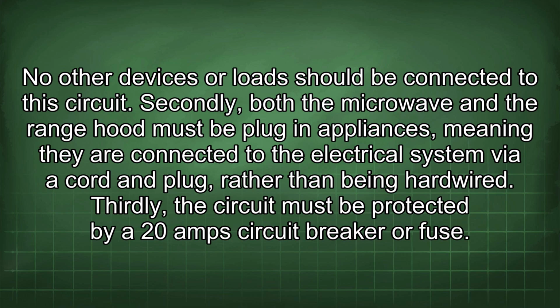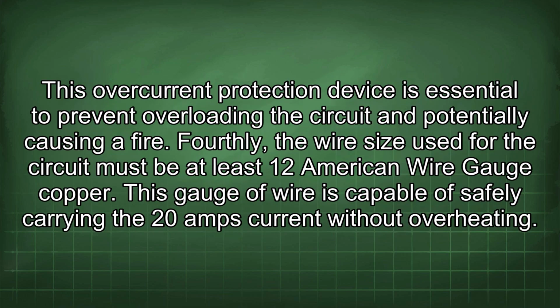Secondly, both the microwave and the range hood must be plug-in appliances, meaning they are connected to the electrical system via cord and plug, rather than being hardwired. Thirdly, the circuit must be protected by a 20-amp circuit breaker or fuse. This overcurrent protection device is essential to prevent overloading the circuit and potentially causing a fire. Fourthly, the wire size used for the circuit must be at least 12 American wire gauge copper. This gauge of wire is capable of safely carrying the 20 amps current without overheating.